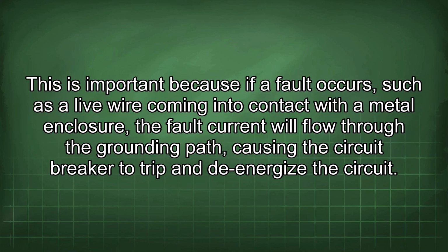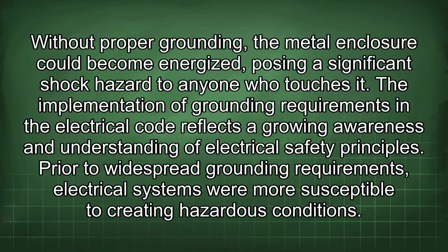This is important because if a fault occurs, such as a live wire coming into contact with a metal enclosure, the fault current will flow through the grounding path, causing the circuit breaker to trip and de-energize the circuit. Without proper grounding, the metal enclosure could become energized, posing a significant shock hazard to anyone who touches it.